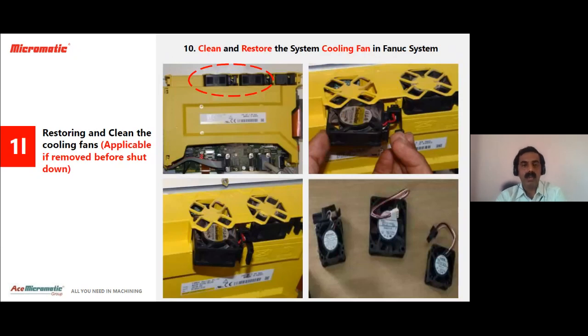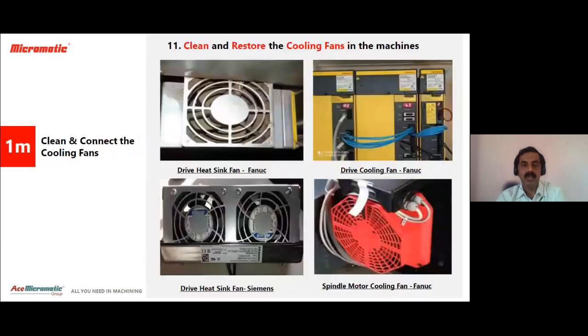There are other fans which also need to be cleaned. We have to clean the drive heatsink fan, which is in a FANUC as shown on the left side of the screen, and below that the drive heatsink fan in the Siemens controller. So drive cooling fan, apart from these two fans, there is a fan of the spindle motor. It is shown in the picture that we also need to clean that spindle motor cooling fan.